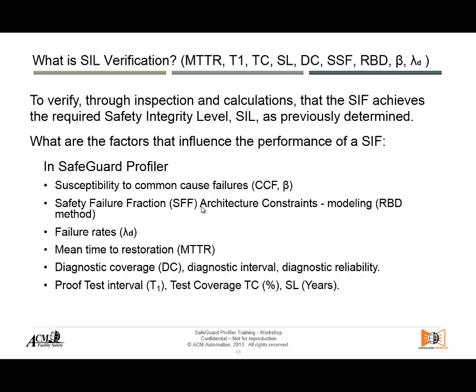Safeguard Profiler will show you what we call sensitivity analysis — how sensitive is that PFD number when you change the failure rate or any other of these factors. Related to the proof test interval is the test coverage factor and the useful life of your equipment. According to the manufacturer, equipment has a useful life of 15 or 10 years. You have to take that into account when considering imperfect proof testing, to add that percentage as discussed before.